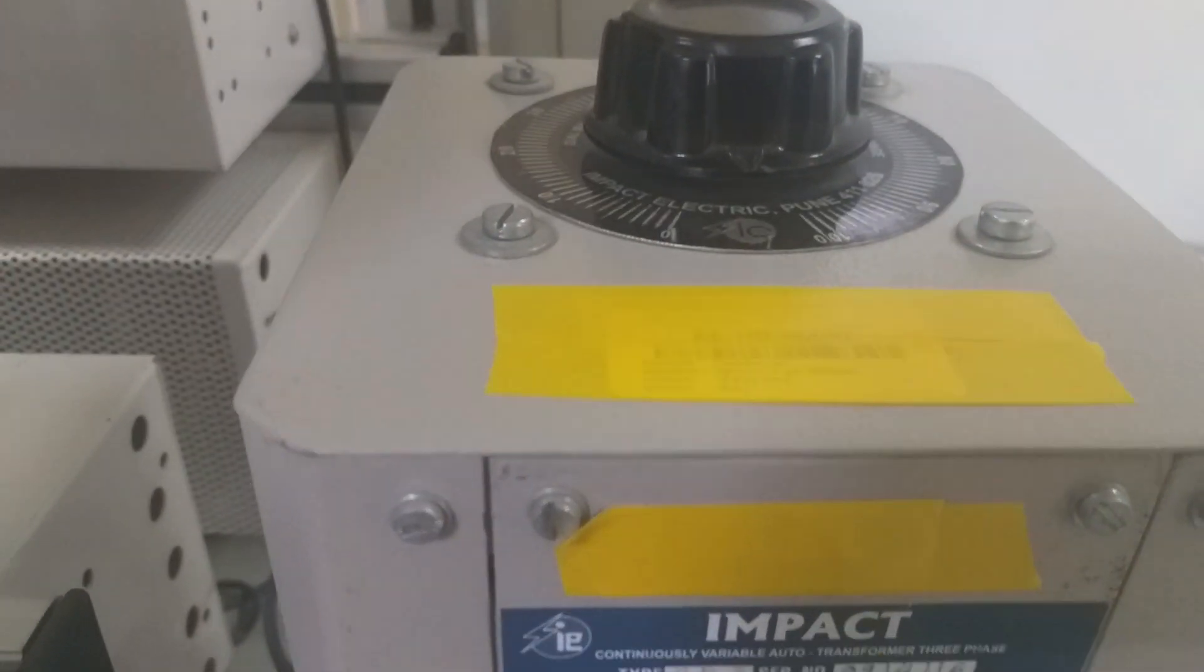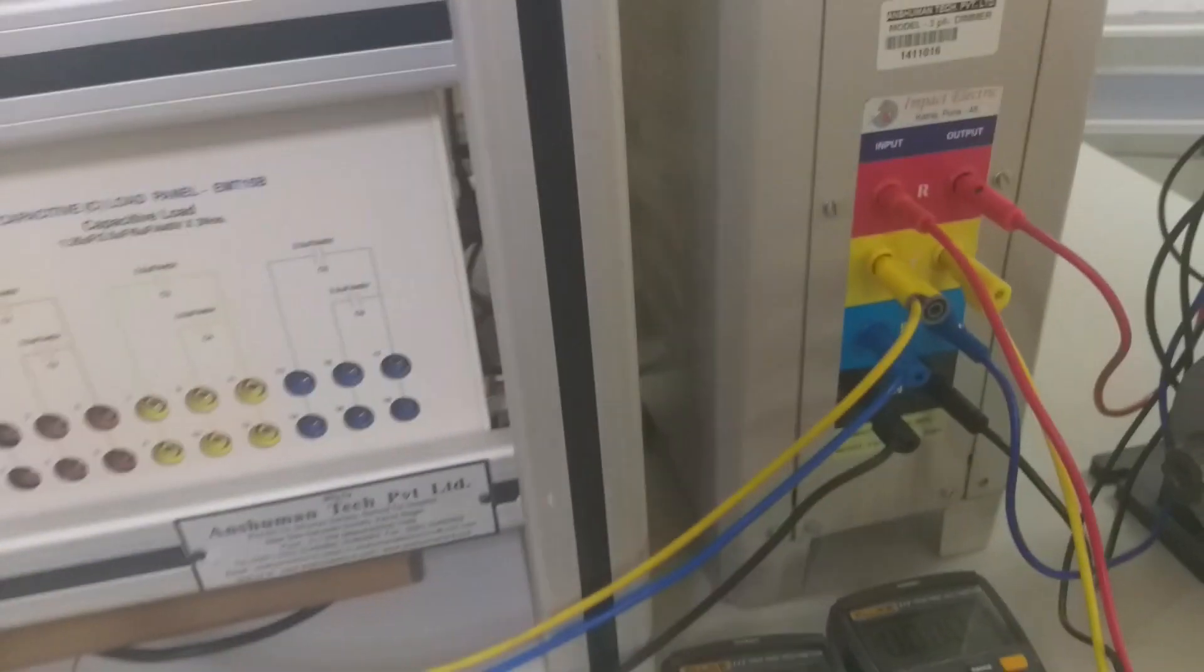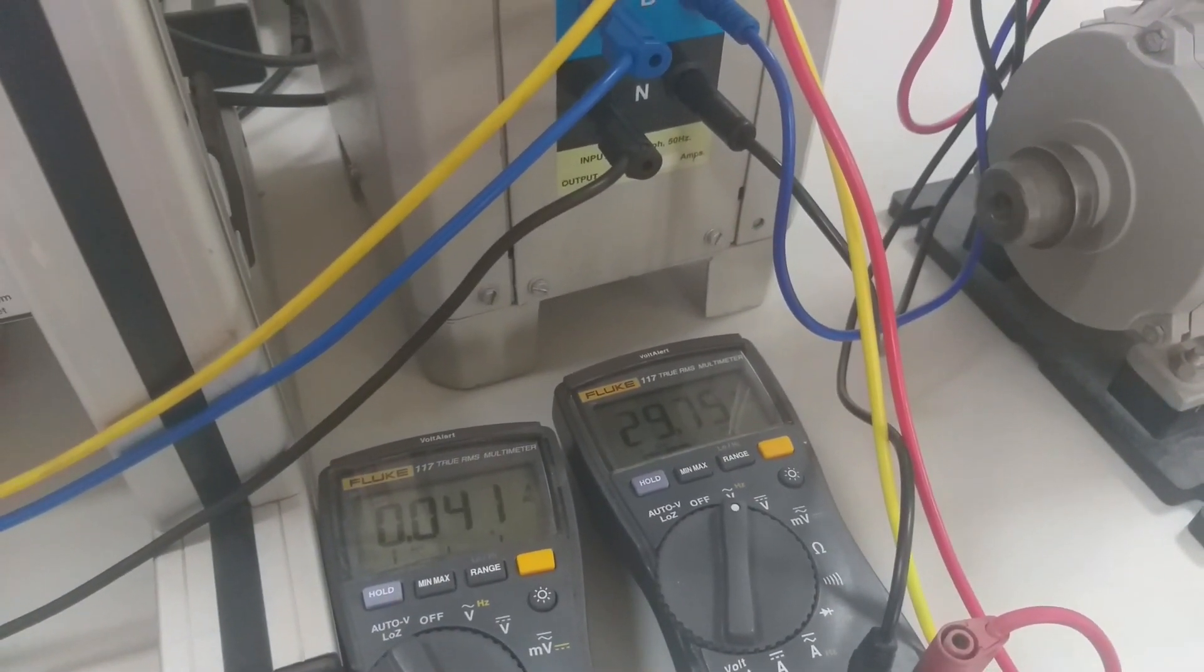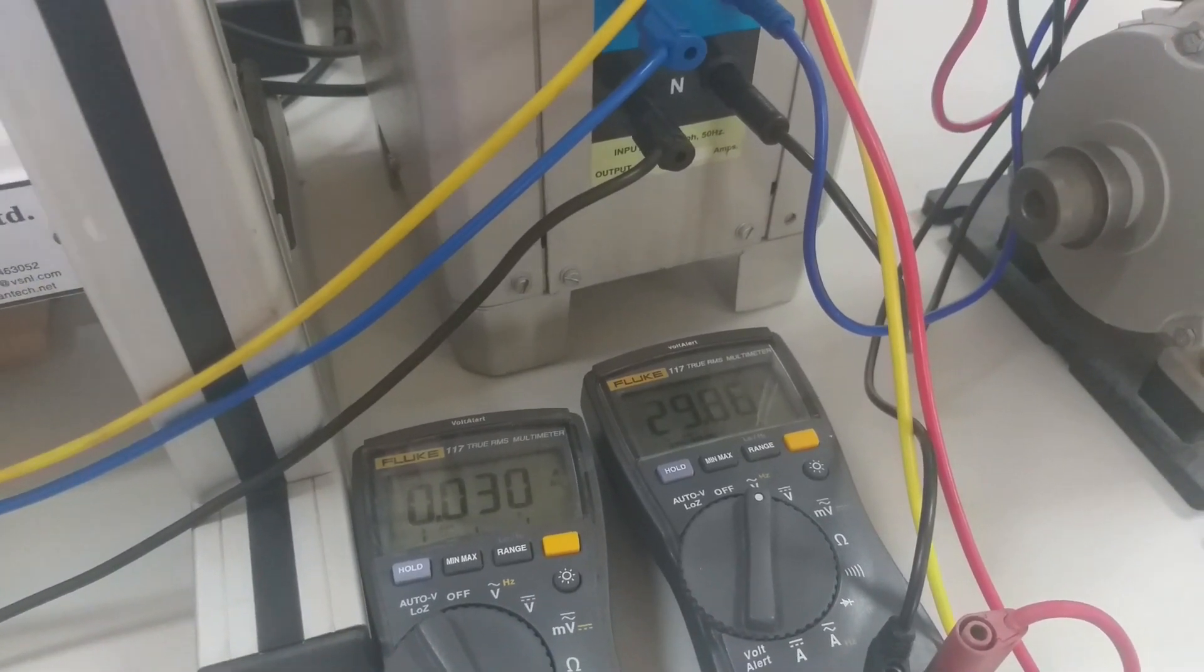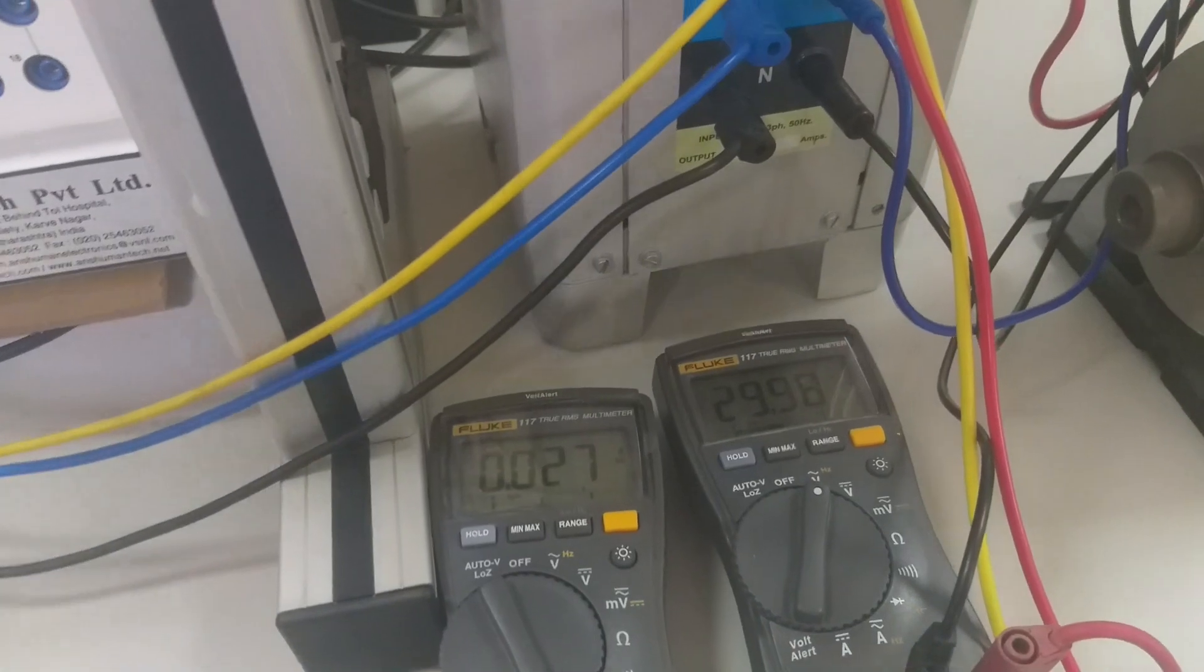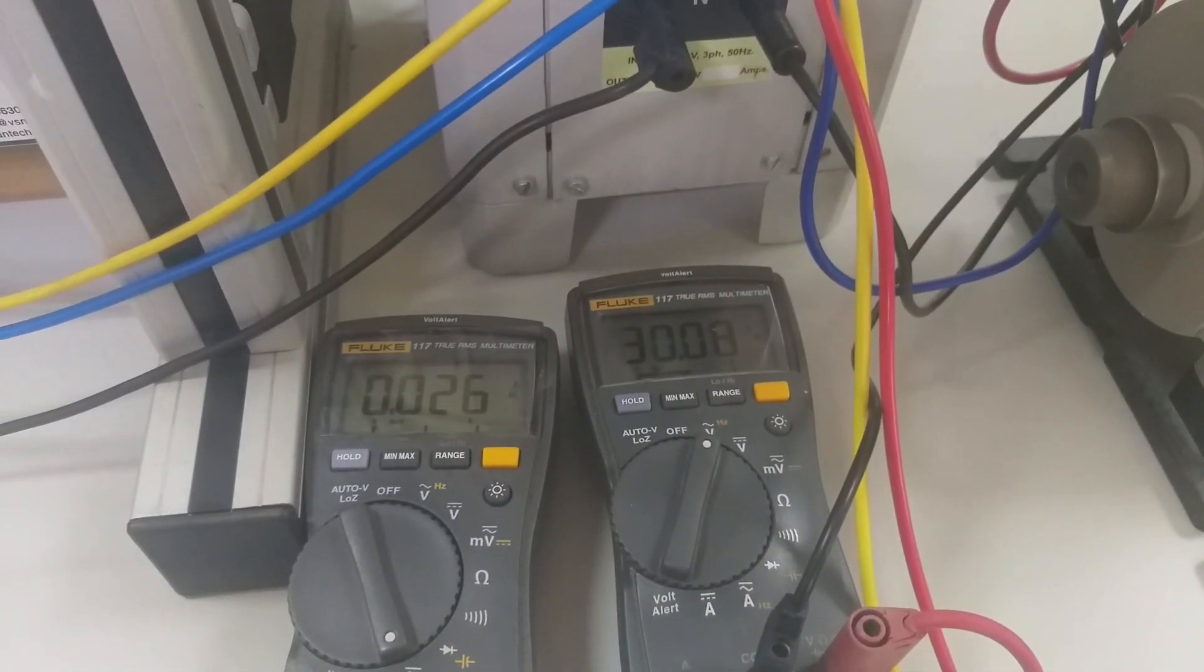Now I keep this auto-transformer setting to the minimum value so that the applied voltage will be very minimum in the initial stage or the starting time of the induction motor. I am going to start now. We have only 29 volts across line one and line two and the current is very less, 0.026.